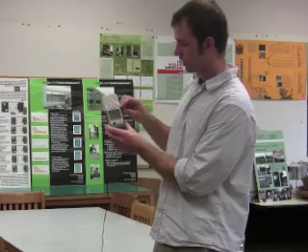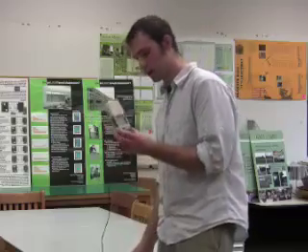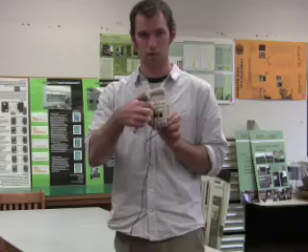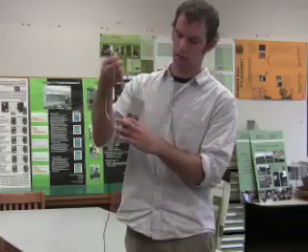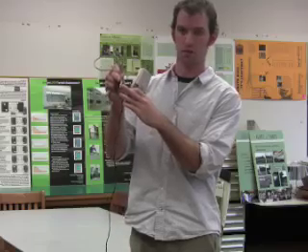One other thing to know about this is that it'll give you instantaneous readings, but if you want to get readings over time, you can launch this with a hobo. You want to use one of the hobo U12s and launch the external channel, and then you'll need to connect your CO2 meter through, it has an Ethernet type port, so you have a cord that has an Ethernet to a input that can go into the hobo.